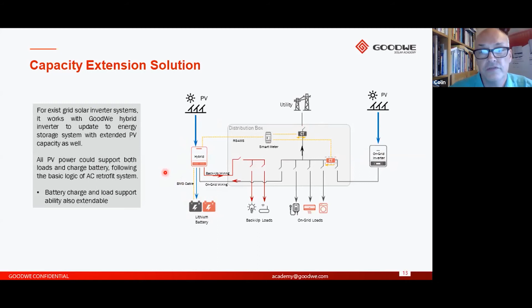What the hybrid inverter will be able to do, because of the CT clamp at the incomer to the property, is detect the excess energy generated from both the on-grid inverter and the hybrid inverter itself. It will use the combined amount of energy to charge the battery, meaning you could benefit from increasing the storage capacity. That's how you can extend the solution.